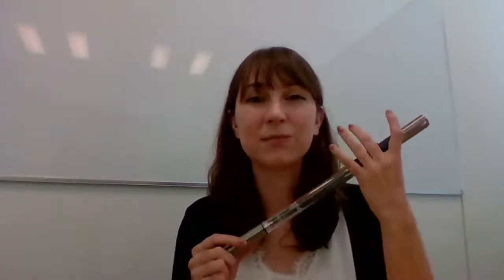Do we have any additional questions? Yeah, we have how to calibrate the instrument. I think this is the third time I've answered this question. We have a calibration oil that you can purchase to calibrate this instrument. However, it does not need to be calibrated as often as other instruments in the Atago line. So it doesn't come with the instrument because you don't really need to calibrate it often. Only when you are noticing some weird fluctuating values or error messages or things that just are not making sense. So normally after a couple of years, it might be something that you want to get the calibration oil for.